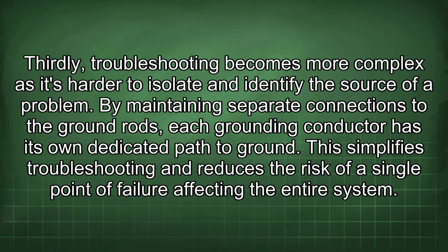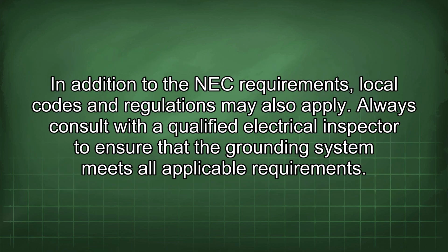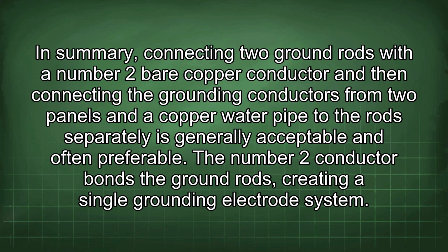By maintaining separate connections to the ground rods, each grounding conductor has its own dedicated path to ground. This simplifies troubleshooting and reduces the risk of a single point of failure affecting the entire system. In addition to the NEC requirements, local codes and regulations may also apply. Always consult with a qualified electrical inspector to ensure that the grounding system meets all applicable requirements. In summary, connecting two ground rods with the number 2 bare copper conductor and then connecting the grounding conductors from two panels and a copper water pipe to the rods separately is generally acceptable and often preferable.